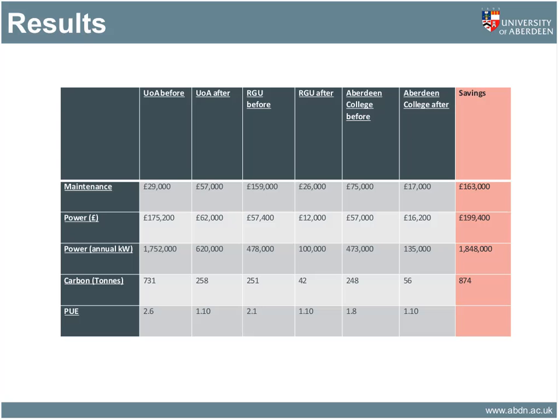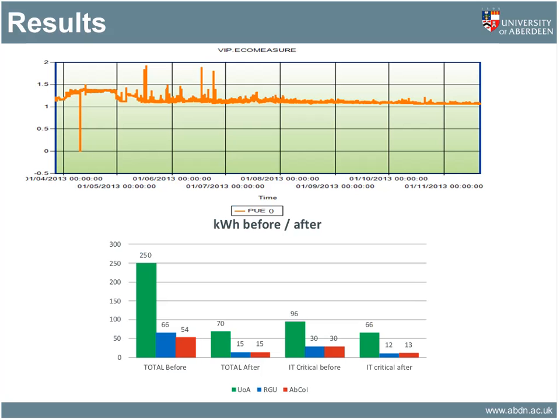One of the questions being asked is, how can you prove it? We have a monitoring system in place, and that's our PUE that we share with all of our partners on a monthly basis. It allows them to see how we're gradually becoming more efficient and effective with our PUE values. The bottom half of the graph shows the power before and after. Getting rid of the inefficient cooling system has had a major impact, but we've also, as Steve was talking about earlier, gotten rid of the old rubbish that was in existence, dropping our critical demand from 100 kilowatts down to just under 70 kilowatts, where we are today.